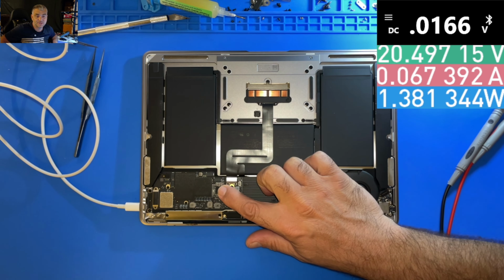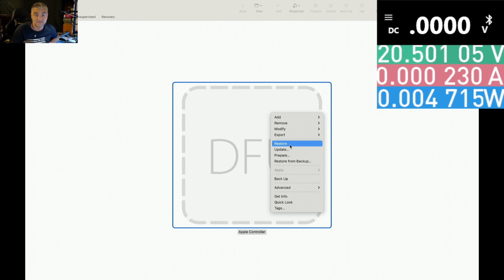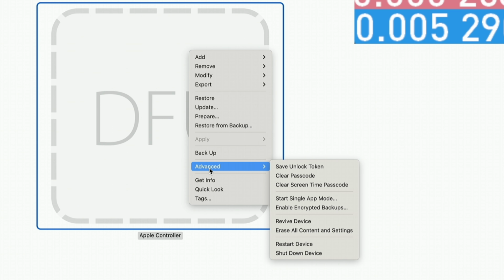Next step, I need to show you a few things, because this is also very important. For example, if there's a unit where you need to recover data, never try to do a restore. If you try to do a restore, it will erase everything and bring it into factory settings, and you will not be able to recover — that's a permanent loss of data. That's why, if the data is critical and the unit came in for data recovery, never do a restore. Instead, you have to go to advanced and choose advanced revive device.